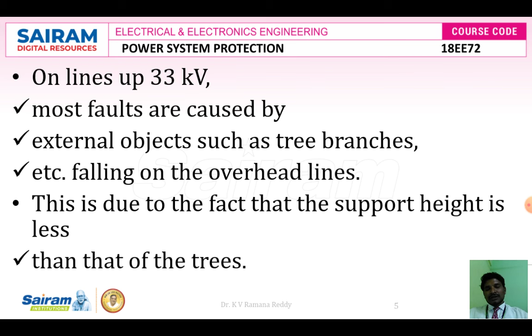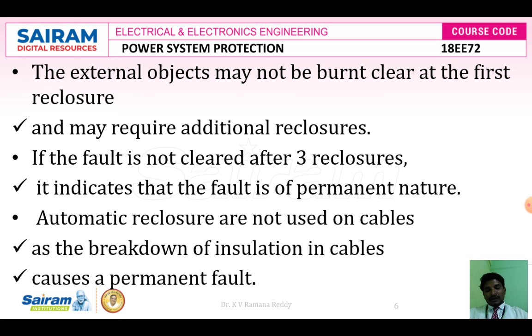it indicates the fault is of a permanent nature. And automatic reclosures are not required for underground cables, because in underground cables, if any fault takes place, it is a permanent fault. For a permanent fault or dead short circuit fault, an automatic reclosure is not required. Definitely human intervention action is required to clear the fault. Usually 3 reclosures are used to clear one fault.